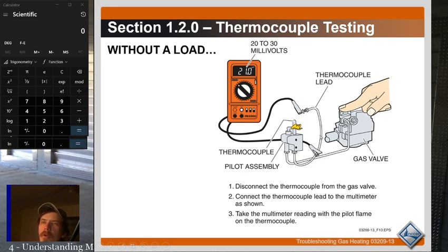Now, if you don't have three hands, right? Because this kind of takes three hands unless you got the clips on your meter, because you got to hold it here, and hold it over there. They do actually make adapters that you can screw in to the thermocouple to allow you to check voltage with it being in place. They do make adapters for that, and it's kind of nice to have around. But if you use that adapter, typically you're going to see a smaller voltage. So my advice is read the instructions that come with that adapter to make sure you know what you're going to read. If I remember right, I think you're going to read 10 to 15 millivolts normally when you use one of those adapters. But it's been 10 to 12 years since I've used one.